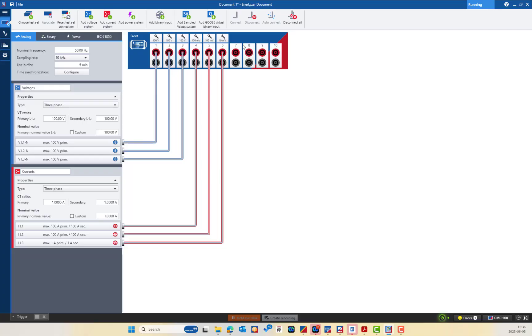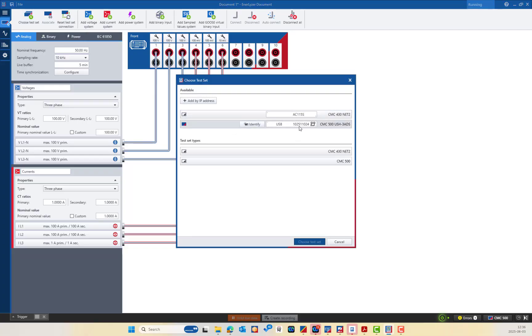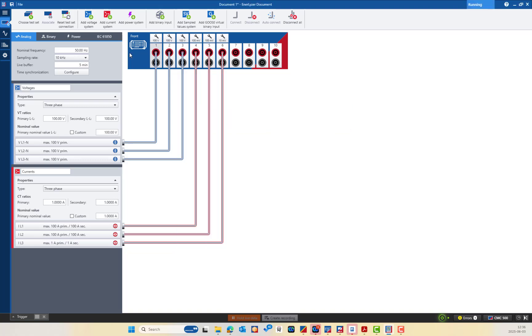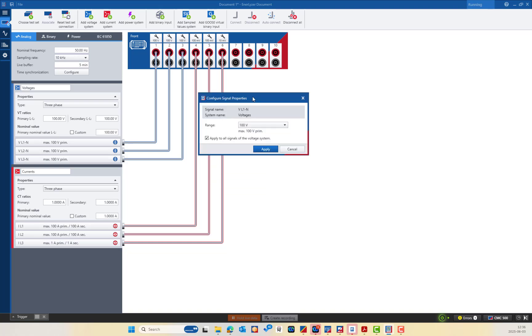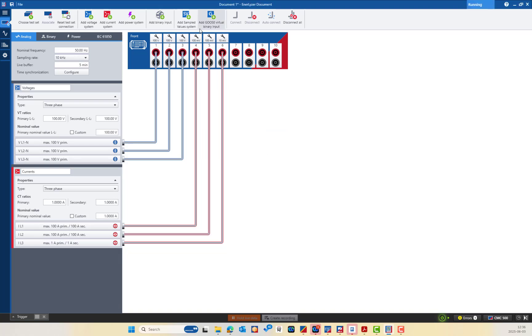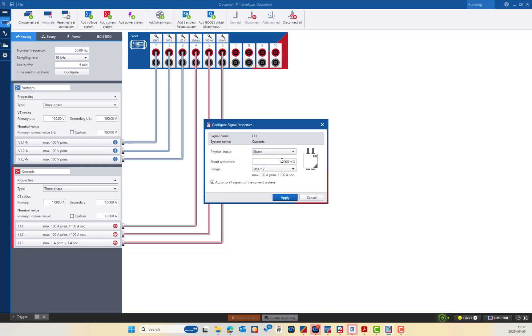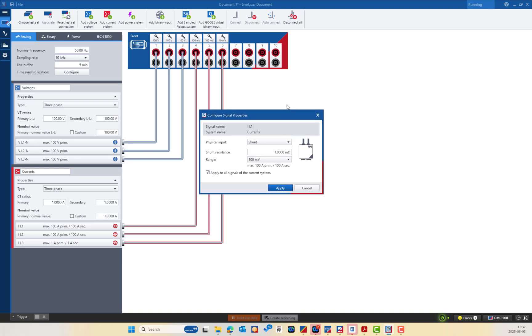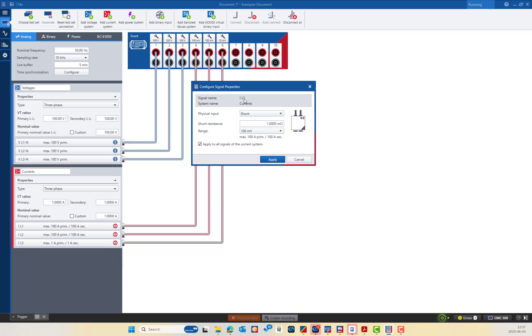Opening the Analyzer module, I select the CMC 500 USH variant connected via USB — it shows online. I configure analog inputs 1 to 3 for voltage measurement with a maximum range of 100V, and there is an option to apply this setting to all three voltage inputs at once. Analog input 4 uses a C-Shunt 1 milli-ohm with a 100 mV range. The CMC 500 also supports a 10 mV range, which is not available in the Analyzer Classic module with the CMC 356.